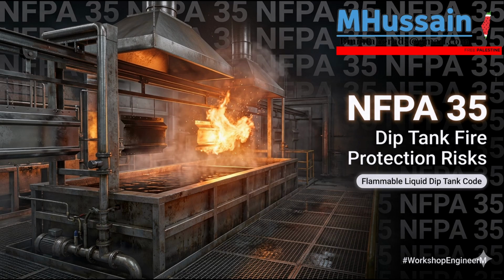And what if you were using pumps instead of gravity? You need a similar rapid shutdown philosophy. You must install emergency switches to immediately kill power to all pumps and stop the flow of fuel. These switches have to be strategically located at the exits from the process areas, at other safe locations, and right at the pumps themselves.